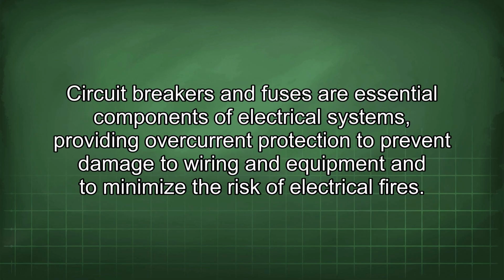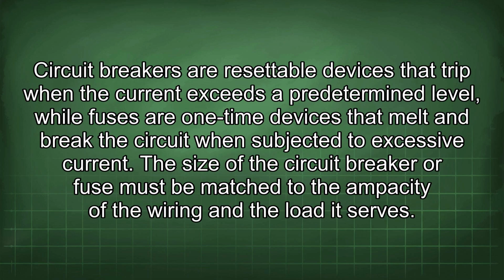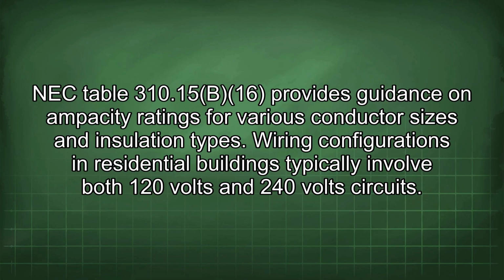Circuit breakers and fuses are essential components of electrical systems, providing overcurrent protection to prevent damage to wiring and equipment and to minimize the risk of electrical fires. Circuit breakers are resettable devices that trip when the current exceeds a predetermined level, while fuses are one-time devices that melt and break the circuit when subjected to excessive current. The size of the circuit breaker or fuse must be matched to the ampacity of the wiring and the load it serves. NEC Table 310.15(B)(16) provides guidance on ampacity ratings for various conductor sizes and insulation types.